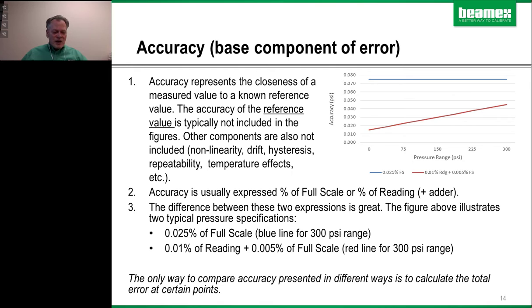Now, I want to give you some concepts. I want to talk about accuracy, which is, I put in parentheses here, a base component of error, versus uncertainty, which is kind of a statistical average of errors. So when you say, how accurate is this calibrator, or how accurate is this instrument, it's kind of a moving target. And here's a definition of accuracy where we're saying that it's the closeness of a measured value to the known reference value.